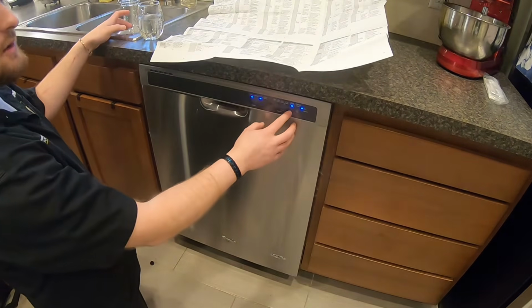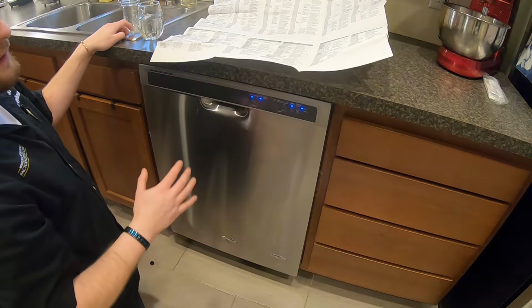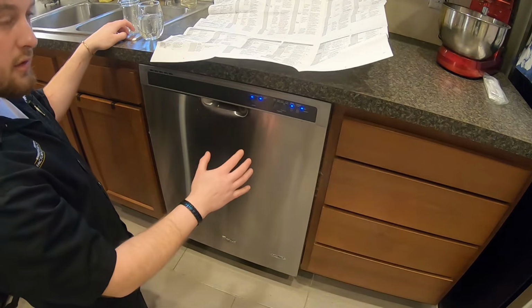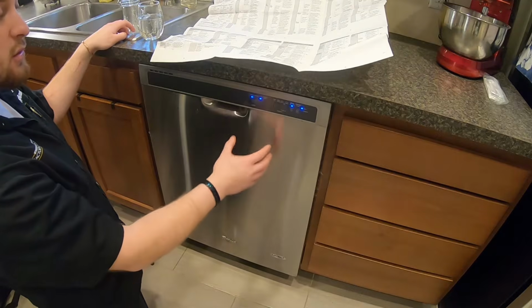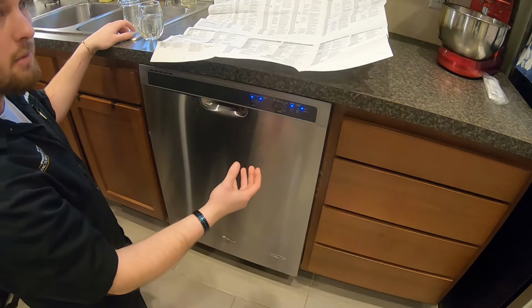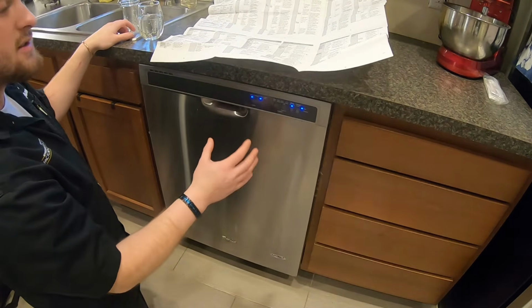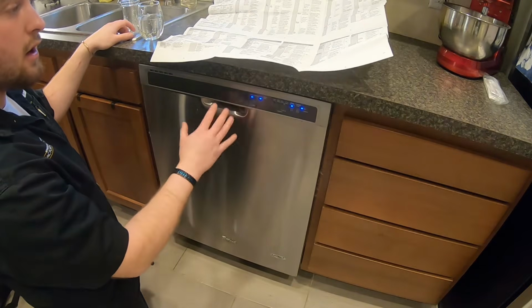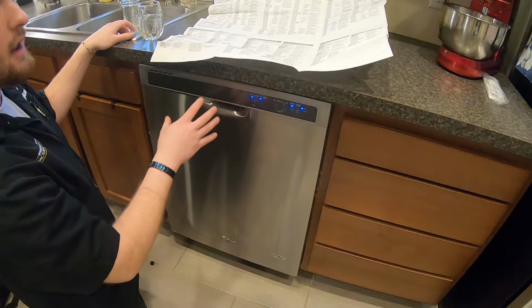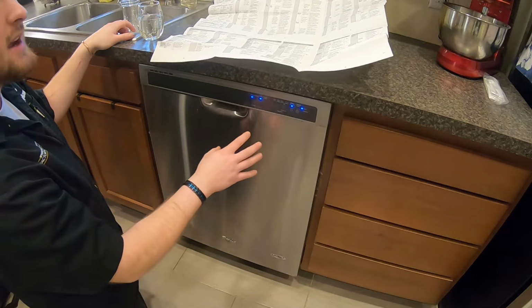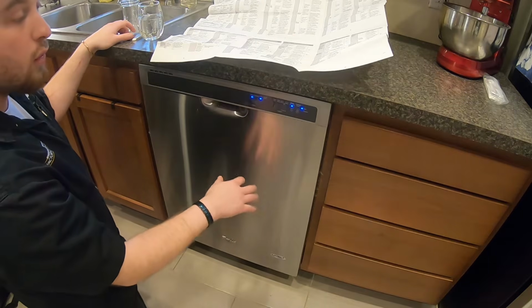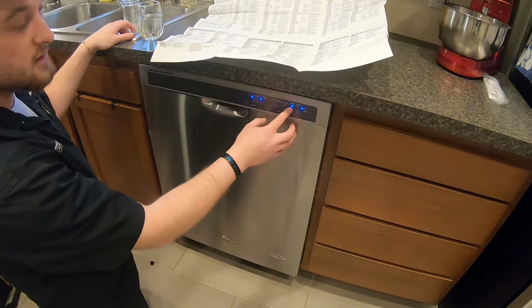According to the tech manual, after it goes through the cycle, once it has drained the water you'll hear the drain pump kick on 3 times. Once that portion of the automatic test cycle is done, it will turn on your heating element. At that point you wait about 30 seconds for the heater to get really hot, open the door, and pour cold water on the heater to make sure it works.